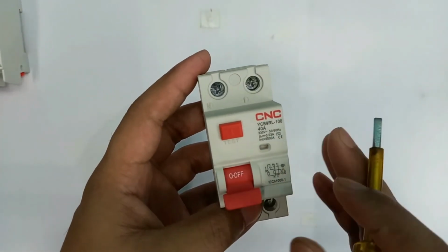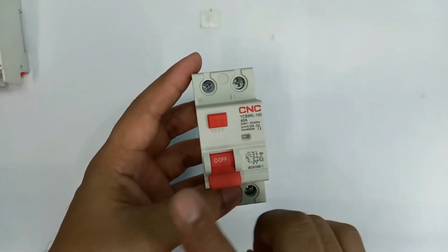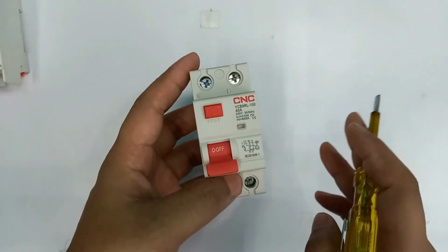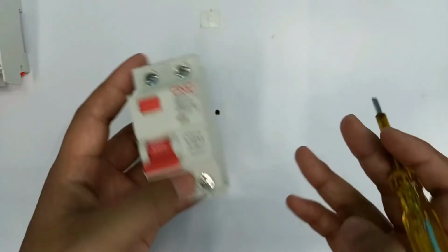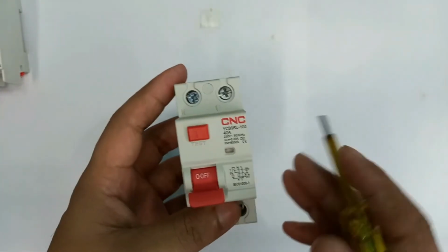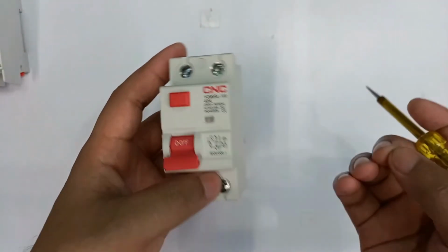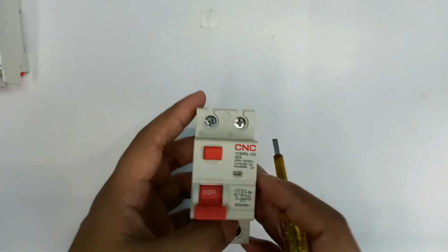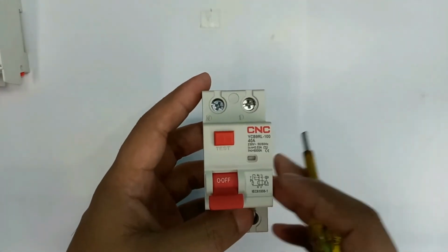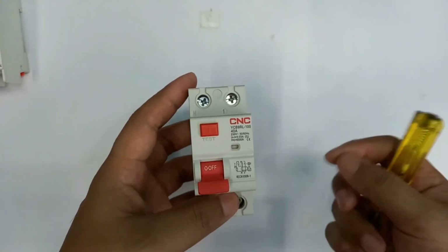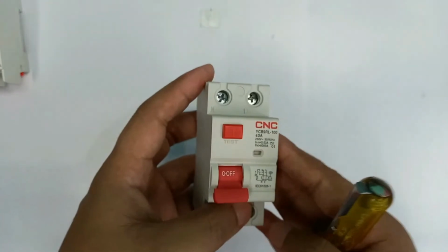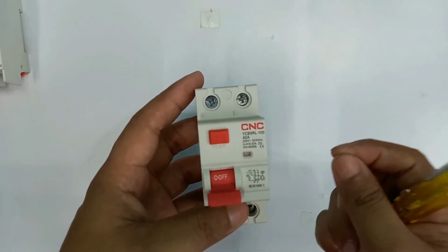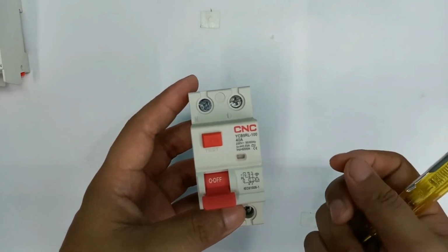If you see a protecting device in an industry that is more than 300 milliampere, or 500, more than 500 and 1000 milliampere, that is mainly used for fire prevention purposes, right? You will see in industry sometimes the wire goes through places where fire could occur, such as areas with some chemicals. So at that time we use a protective device with a high milliampere capacity. Are you getting my point, what I want to say?